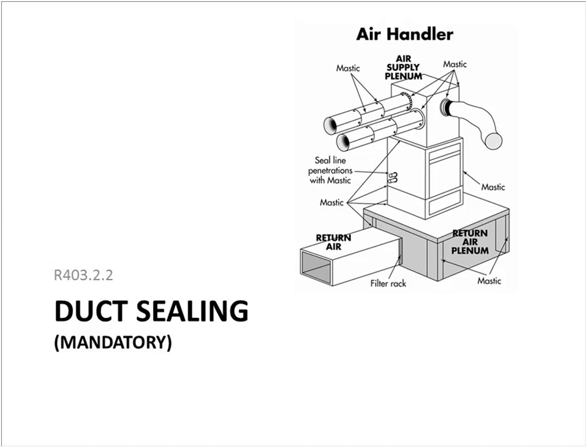And we also want to make sure that all the penetrations are sealed in the air handler itself, and that we have a gasketed cover on the filter housing, because when we do our testing, whether it be for total leakage to the outdoors or just total leakage, all those areas are cumulative, and it doesn't take very many openings to fail a test. So penetrating lines through the evaporator housing, the return boots where they're connected to the air handler body, all of those need to be sealed. And they show all the joints sealed, but even the long seams on the duct runs themselves are best sealed if you want to keep that leakage to a minimum.